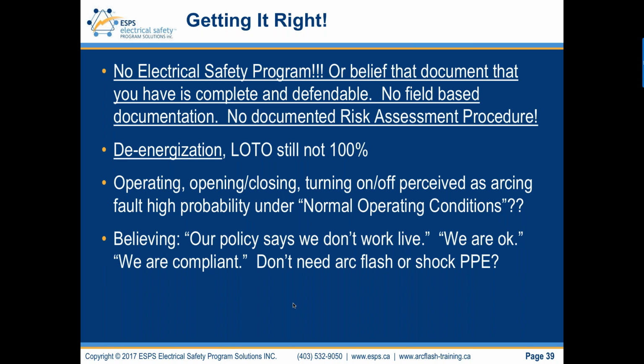And then there's no documented risk assessment procedure to start with, which is a mandatory requirement from 70E and Z462's perspective. So as far as hierarchy of controls, we'll just group them here and continue with the webinar. But de-energization, I'm still seeing lockout, tagout deficiencies in the field. So that shouldn't be there. But again, this is the problem. Occupational health and safety is an evolution, a continuous improvement model. So fine, I see some lockout, tagout deficiencies when I'm in the field with clients. I identify them for them, and then they have to mitigate them.